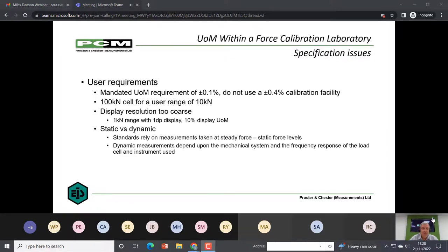The display resolution is too coarse. So if you've got a 1 kilonewton range with a 1 decimal resolution, the uncertainty of the device under test is 10%. You're not going to get great resolution. And then finally, static versus dynamic. All the standards that I've mentioned before, including those that we carry out, all the measurements are taken at steady state, at static force levels. There is very little to follow when it comes to dynamic measurements. And realistically, you need to take into much more consideration the frequency response of both the load cell and the instrument used with regard to the dynamic measurement requirements that you're going to conduct.